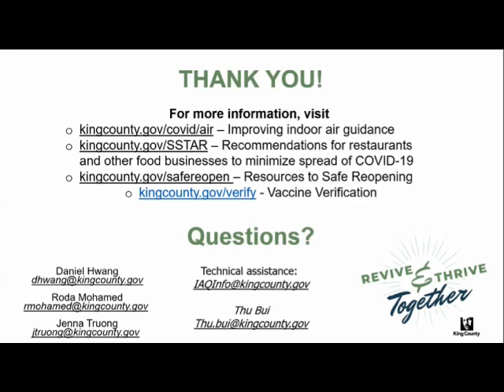Larry Artman asked about Synexis biodefense systems — used in hospitals — and whether the program publicizes them as a best practice. In response: we do not necessarily recommend items to add to HVAC systems that put other substances into the air. This specific technology adds dry hydrogen peroxide to the air, and we don't recommend adding things to systems that could potentially put more pollutants in the air if they react with something else already present. What we recommend is upgrading HVAC filters to MERV 13 or higher, having regular HVAC maintenance including replacing filters, and ensuring the system is cleaned and functioning properly. The only other thing we would recommend similar in nature is upper-room ultraviolet irradiation — a UV light at the very top of very tall-ceiling rooms that helps kill germs. Beyond that, we are not currently recommending any additional technology to add to HVAC systems.